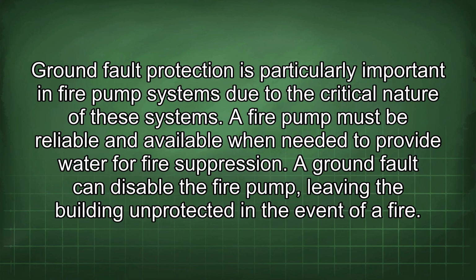Ground fault protection is particularly important in fire pump systems due to the critical nature of these systems. A fire pump must be reliable and available when needed to provide water for fire suppression. A ground fault can disable the fire pump, leaving the building unprotected in the event of a fire.